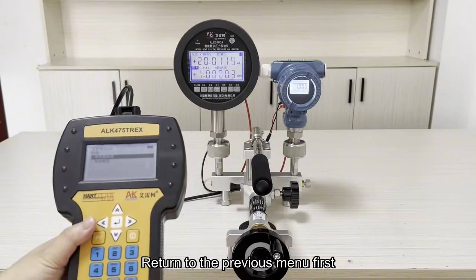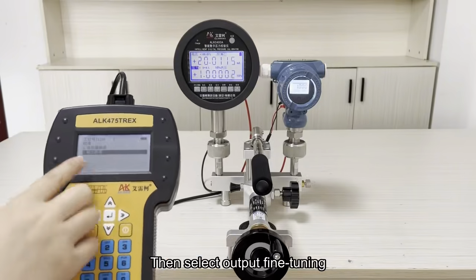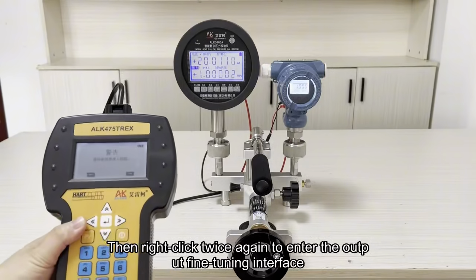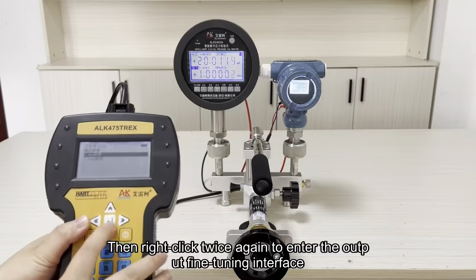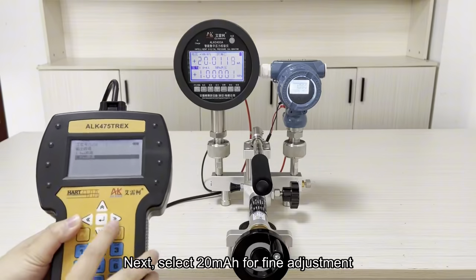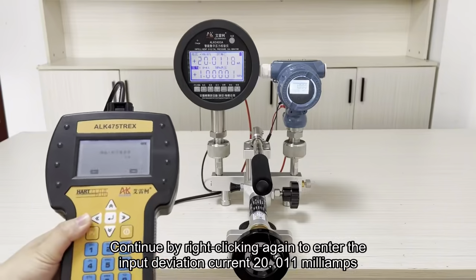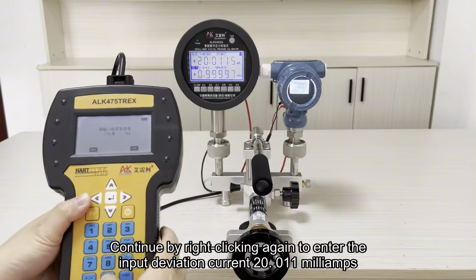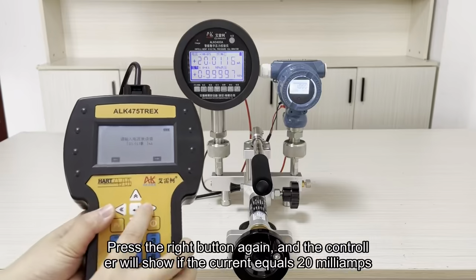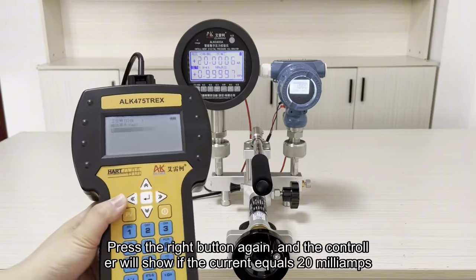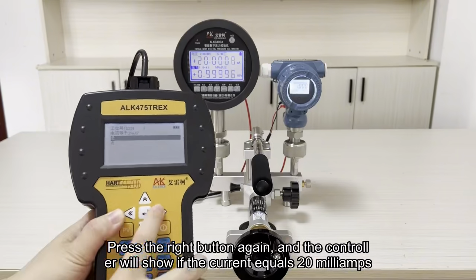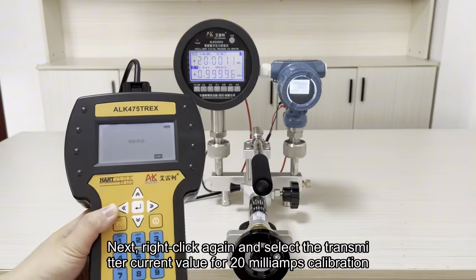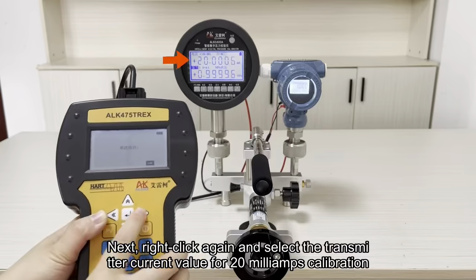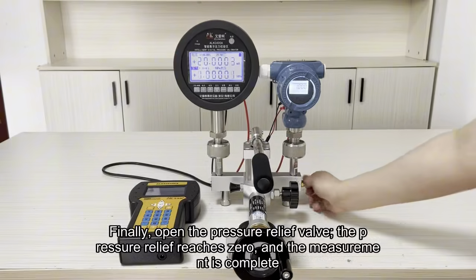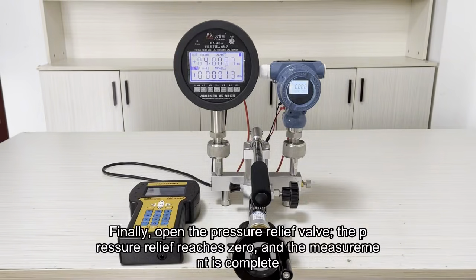Return to the previous menu first, then select Output Fine-Tuning. Then right-click twice again to enter the Output Fine-Tuning interface. Next, select 20 mA for fine adjustment. Continue by right-clicking again to enter the deviation current 20.011 mA. Press the right button again, and the controller will show if the current equals 20 mA. Next, right-click again and select the transmitter current value for 20 mA calibration. Success. Finally, open the pressure relief valve. The pressure relief reaches 0, and the measurement is complete.